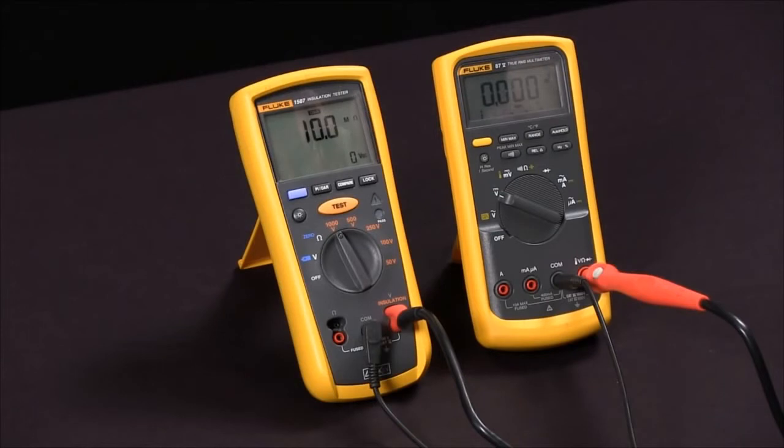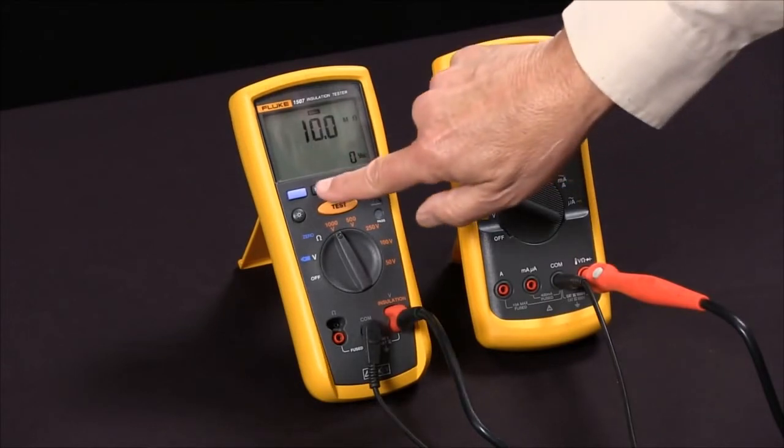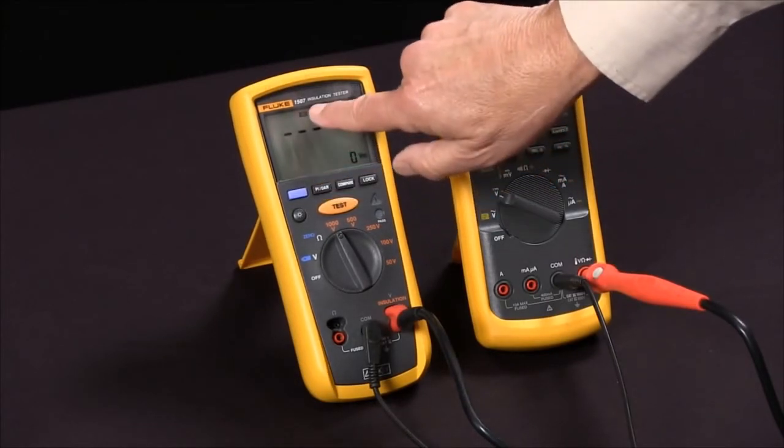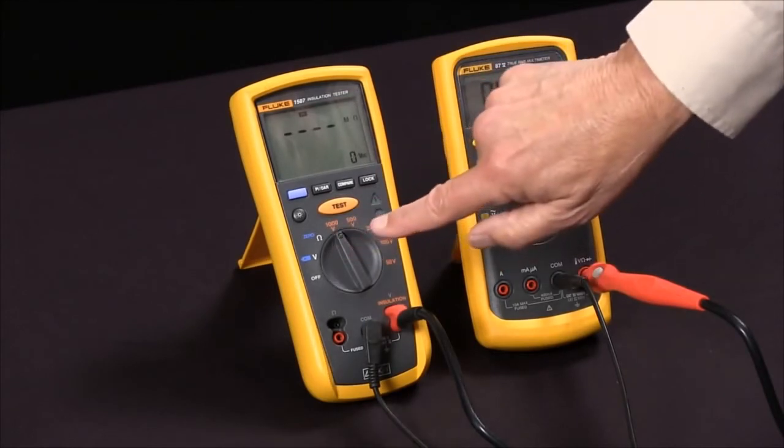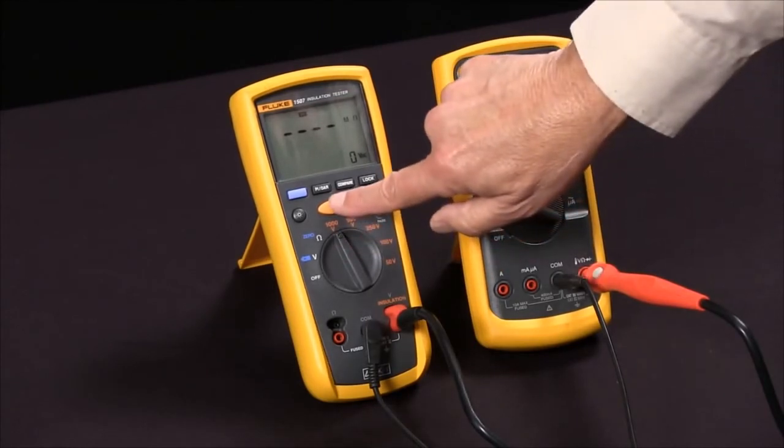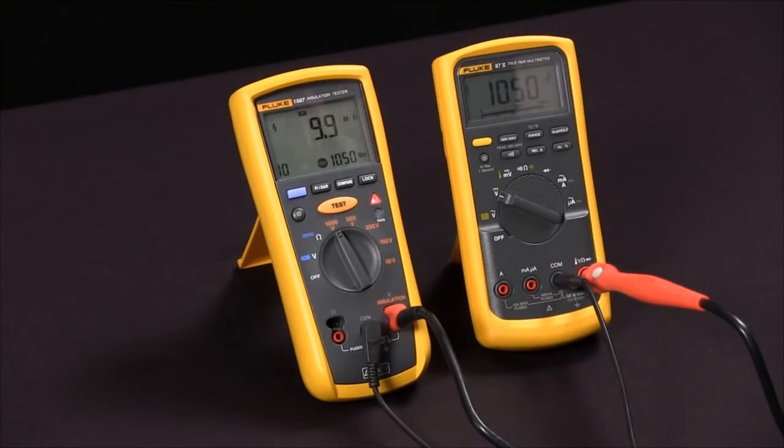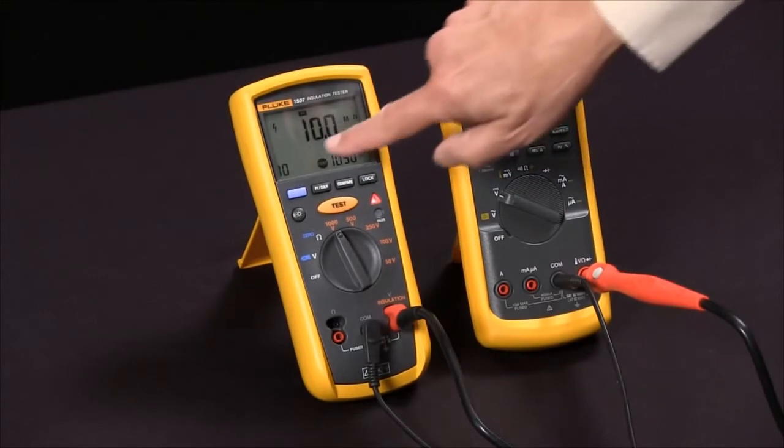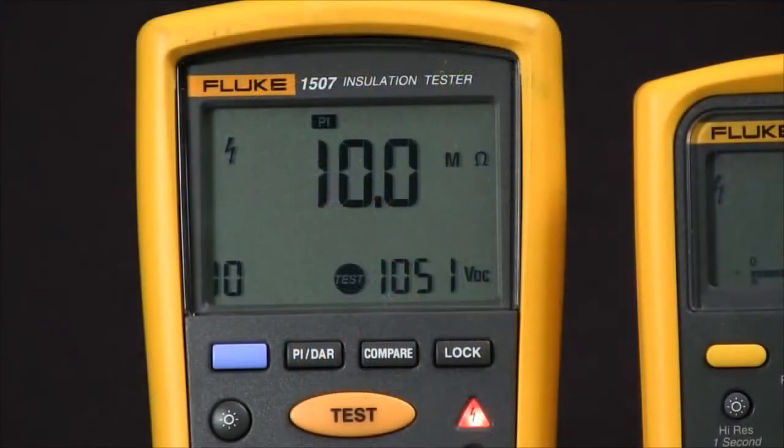Polarization index is done the same way. I select polarization index, 1,000 volts, and I push the test button. It begins a 10 minute test, so you see 10 minutes, and that will count down. At the end result, it will show the ratio.